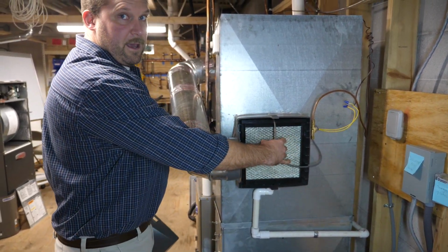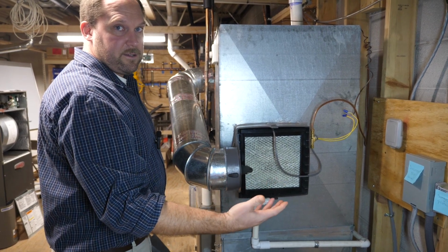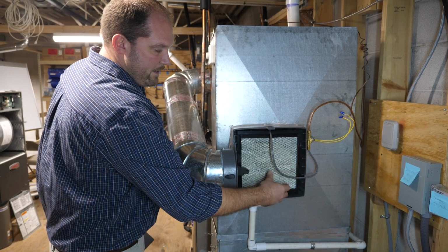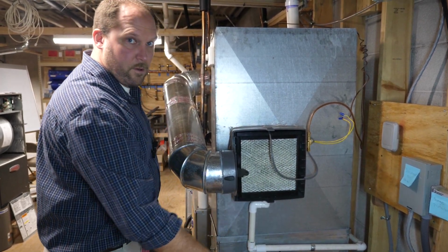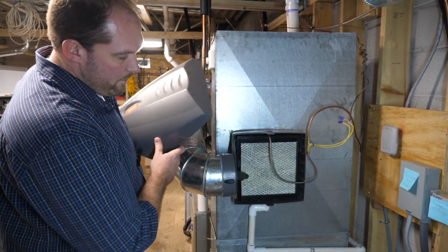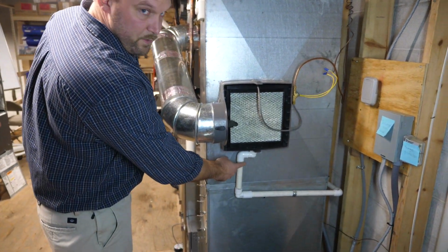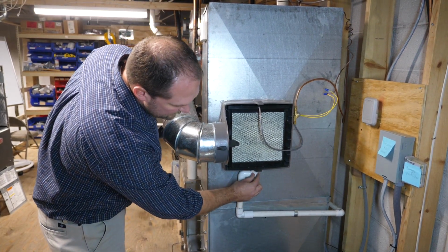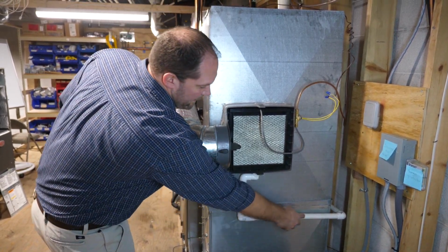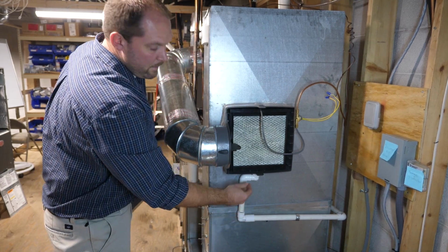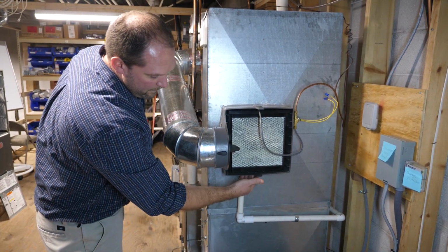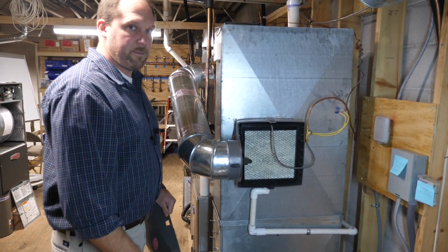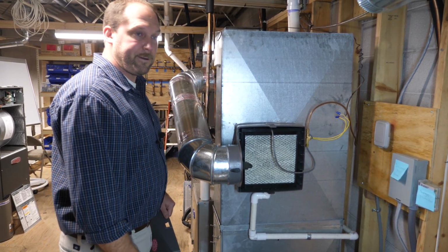The condition of the pad, if it hasn't been changed in a season, it's several years old, the water comes outside of this pad and it can drip down here and then get onto the floor. The other area would be this drain here, because all the water comes from the top and comes all the way down and then comes out this little tube at the bottom. If this gets blocked in any way, water will come from up here out and then splash onto the floor. So those are the three common areas that typically you'd see water coming from a humidifier.